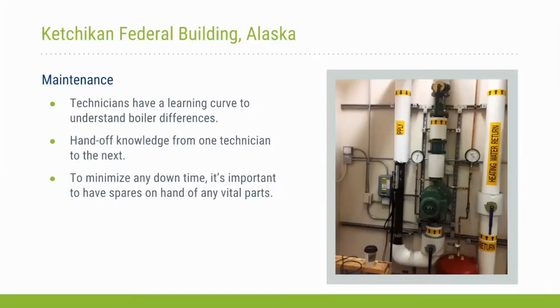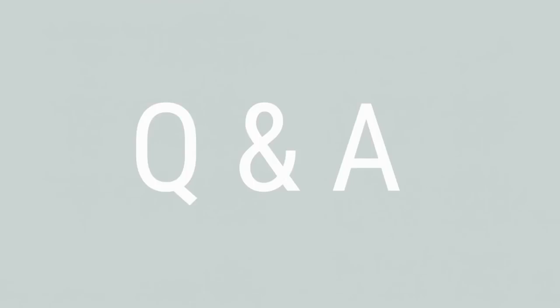And how does that ash build up? Clinkers generally occur for a few different reasons, mainly poor quality of fuel, or if your boiler isn't being cleaned out regularly. With this one, there is an automated system where it helps push all that out. At the same time, for preventative maintenance, when the ash bin is cleared, the O&M technician is looking for the status of clinkers. If there's an increase in that, you want to make sure that everything is running and do a little digging and make sure everything's running.